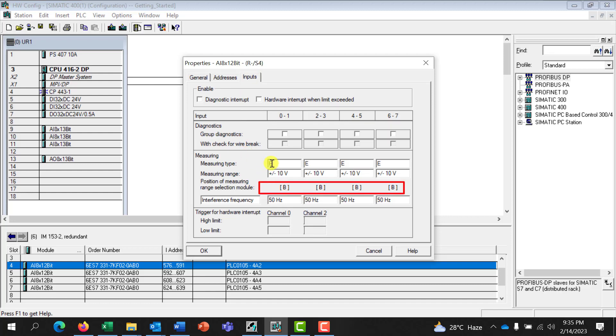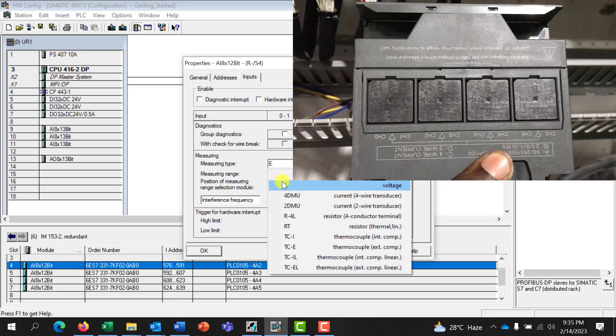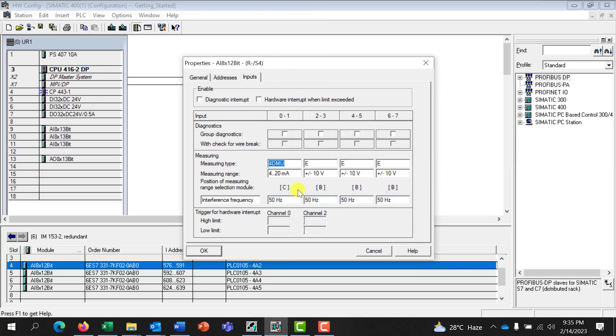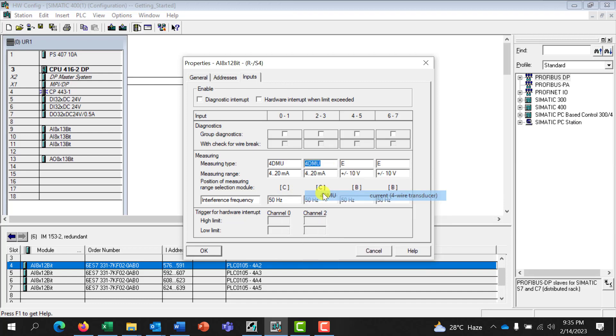And then when we look at the box at the base with the B written in it, which means the hardware is also set at point B. Now let's change it to 4 to 20 milliamps. So I select for the first one, 4 wire, and then select for the next one.